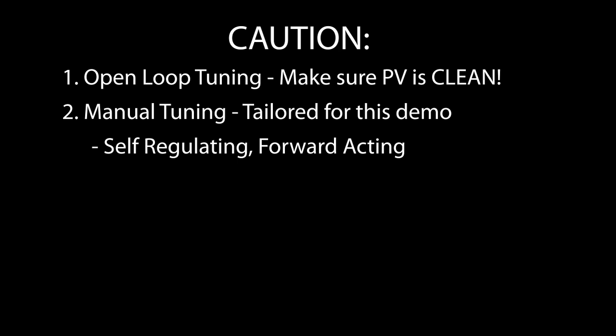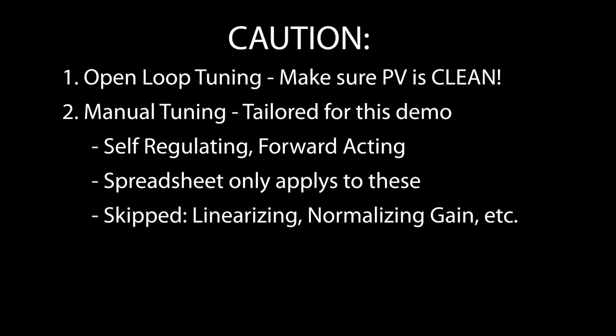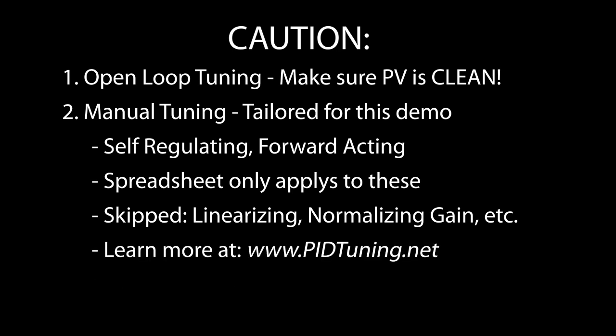The manual tuning we did in this video was for this specific self-regulating type of system. Don't assume that what we did here will work for all systems and don't assume my spreadsheet will work for your system until you've taken the time to understand how the method works. I skipped some things that I knew weren't important or required for this demo, but they might be real important to your system. Things like linearizing the system, normalizing the process gain, etc. I'll show you how to do some of those in future videos. Check out the PID Blueprint website to see how to do other kinds of PID systems and to learn more about this method.